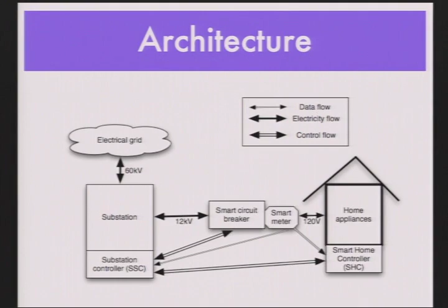So the control time loop over here is basically from here to here, right? So the communication delay actually is not difficult. That's pretty easy to do, okay? In other words, the round trip time from the substation to the smart home controller is probably under a millisecond for most situations, because the substations are fairly close by, under 20 kilometers. Okay. In terms of sensing, yeah, right.